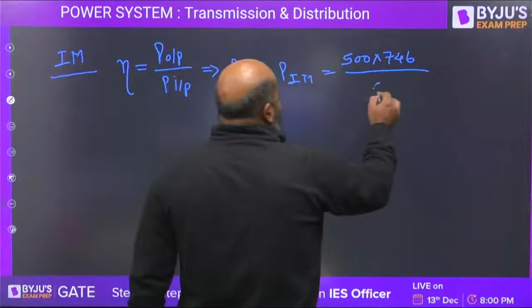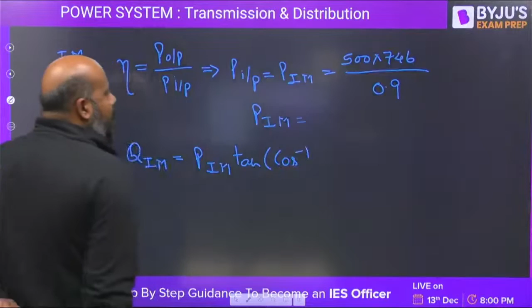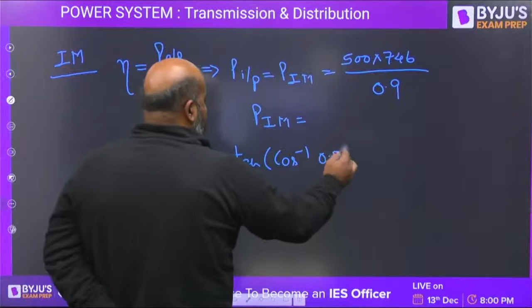If you know the power factor, you can also write the reactive power taken by the induction motor from the supply, that is P induction motor tan phi, where phi is cos inverse of the power factor. What is the power factor? 0.8. Both the values P and Q you can solve. Please tell me the value for P induction motor, because Q you must be getting somewhere around 310.83 kilovolt ampere reactive. Yes or no?